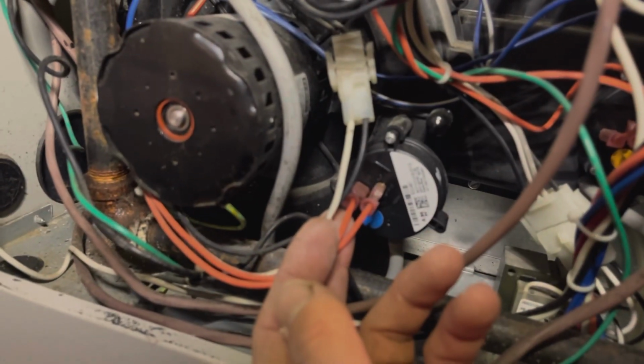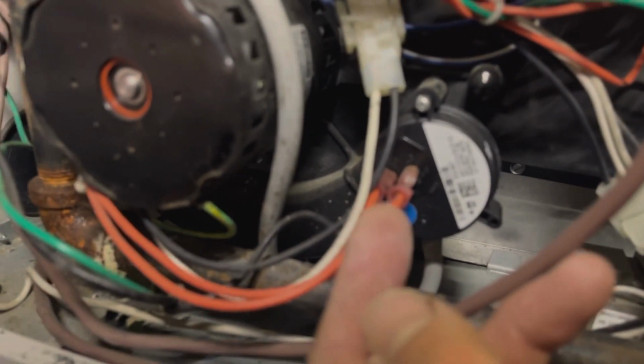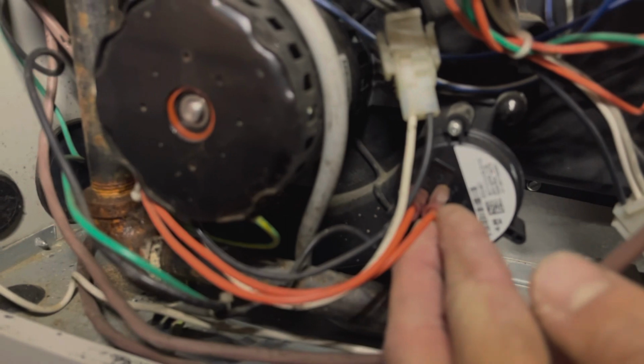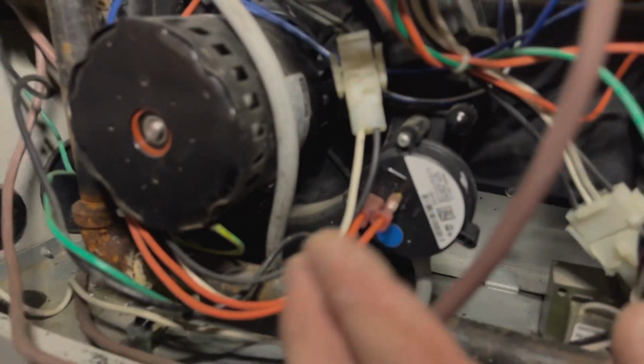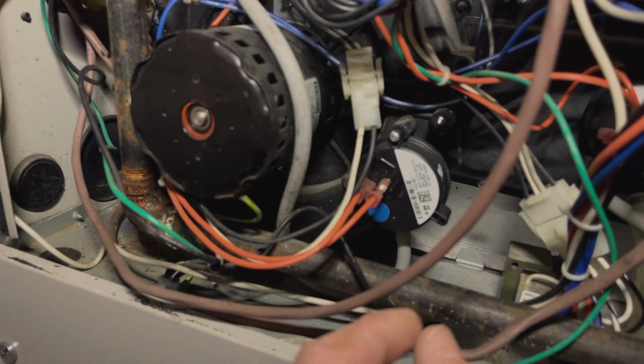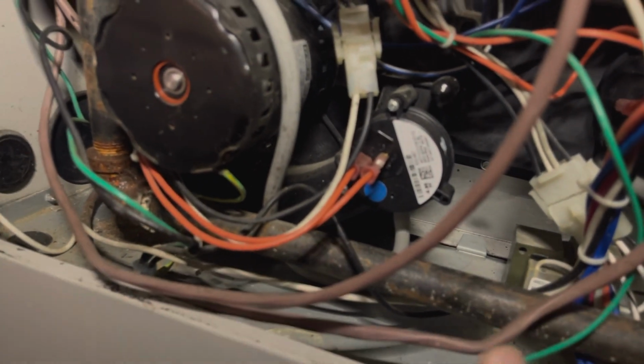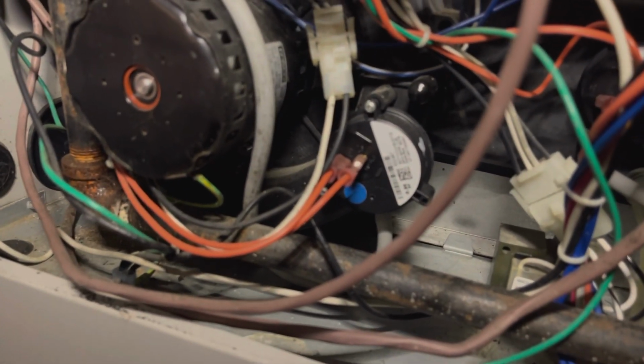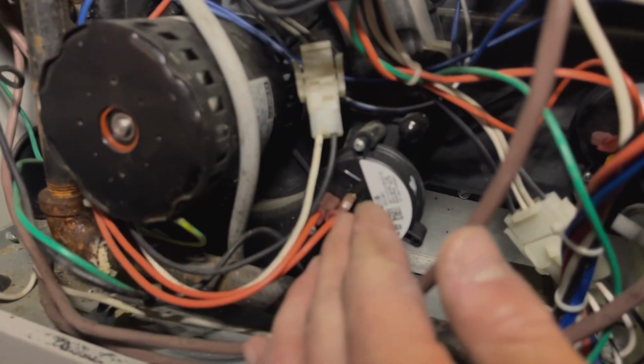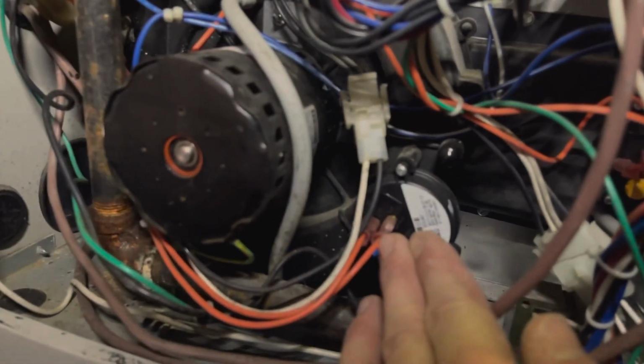If your pressure switches are an issue, they will give you a pressure switch open or closed fault. So what can happen is there's a little rubber-like seal that opens and closes anyways, and they can get stuck open or closed, and you'll get an open or closed fault. So usually, also of course, check that your wires are connected and not corroded and whatnot.